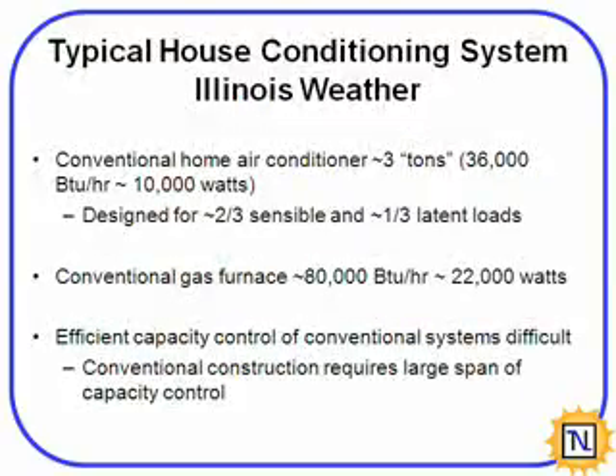Looking at conventional conditioning systems for places like Illinois, usually they'll size, or oversize it, I should say, for the square footage of your house. So for a few thousand square foot home, you'll have about a 3-ton air conditioner, about 10 kilowatts. In its design, roughly 2/3 of this is designed for the sensible, or bringing the temperature down, and about 1/3 of it is for the latent loads, or dehumidifying the air.